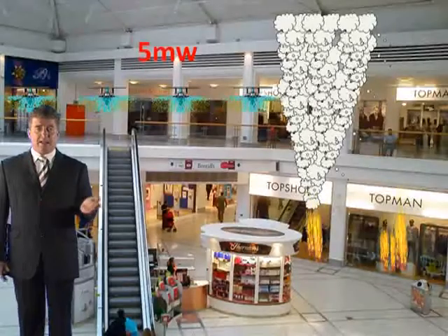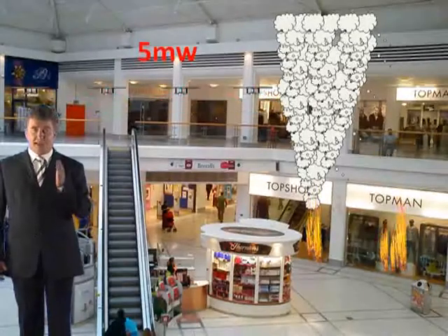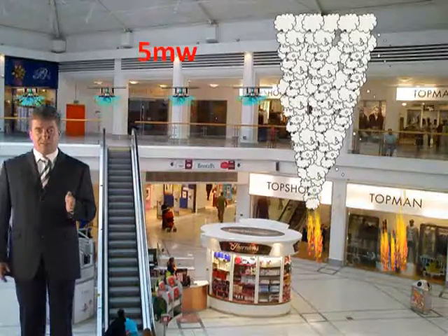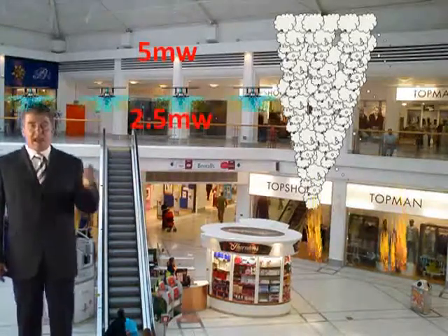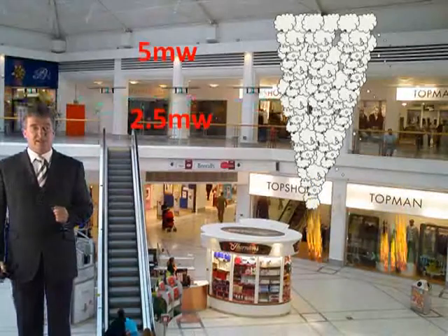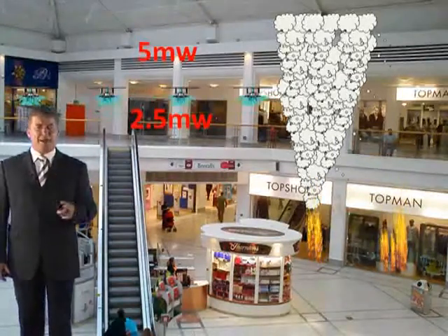Where do you get your design fire size from? In a shopping centre, for example, if it's sprinklered, you're going to get a 5 megawatt fire. If it's a fast response sprinkler, you get a 2.5 megawatt fire. Anything less than that, I want to see where the risk assessment is. Because if you design it on 1.5 megawatt, how are you going to maintain that standard? It's not reasonable. For example, again, in the atrium, if you're going to design a massive atrium and say, we're going to make it totally sterile, we're going to assume a 1 megawatt fire. The biggest problem is, how do you manage that? How do you make sure no one brings anything into that atrium? So again, this must be specified and must be passed across to the end user.